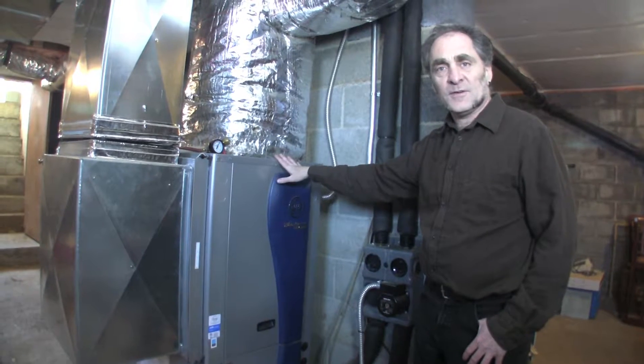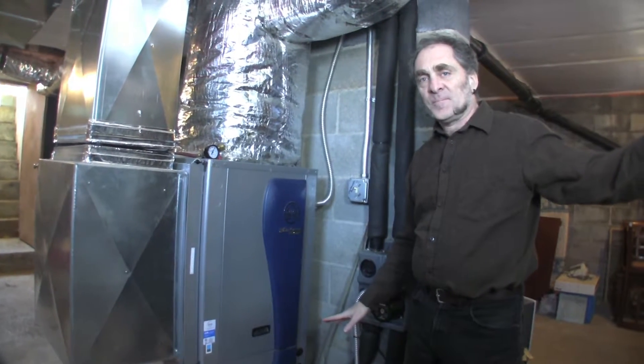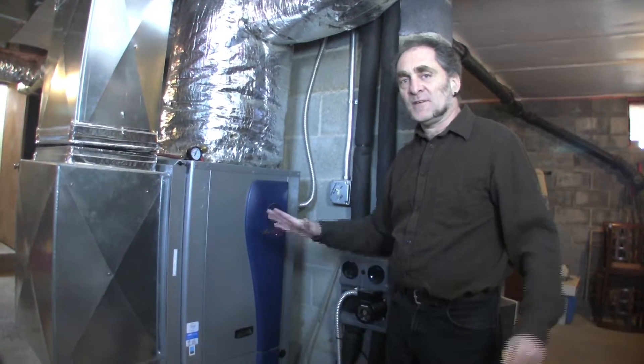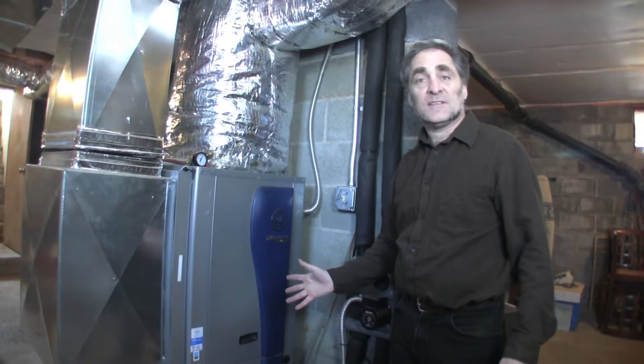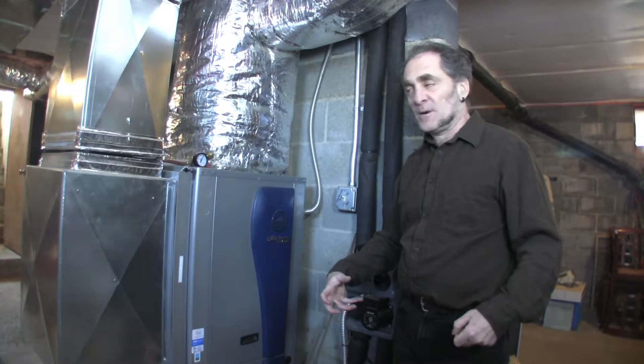If you had an air source heat pump, it's pulling from the outside air, and when it's warm-ish outside, no problem — it works very well. But as soon as it gets too cold, there's just not enough ambient heat in the air outside for it to work properly.